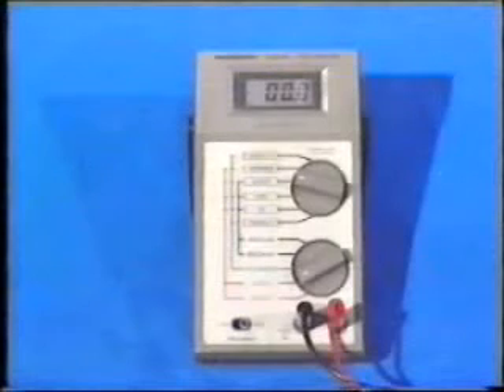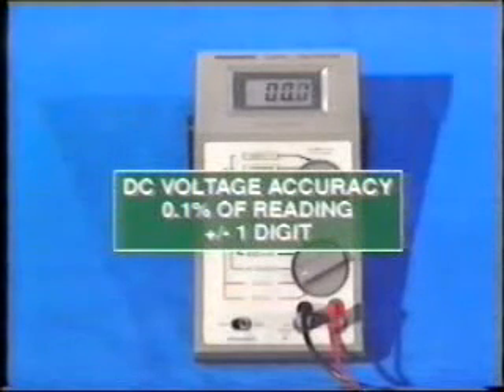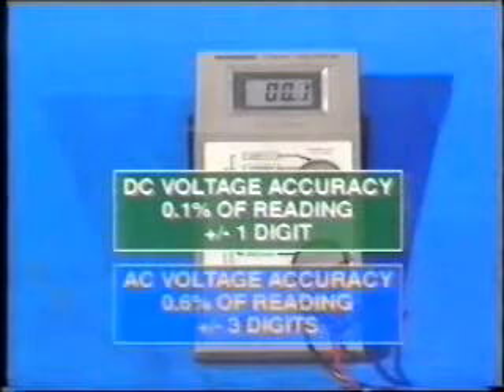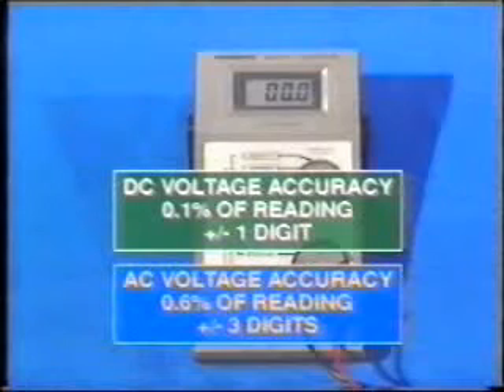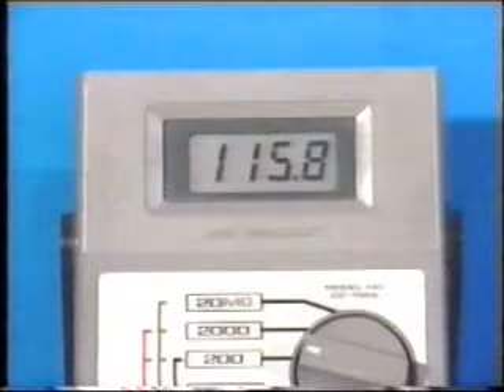When using a DMM, be aware that the accuracy of measurement may not be the same for different types of measurements. For example, with this meter, the specification indicates a DC voltage accuracy of 0.1% of the reading, plus or minus 1 digit. However, if we select this instrument to measure AC voltage, then the specified accuracy falls. The tolerance for error is now 0.6% of the reading, plus or minus 3 digits. This is for a frequency within the normal range of 45 Hertz to 2 kilohertz. Note that an error of, say, 3 digits on the scale has less significance on a full-scale reading than one at the lower end.